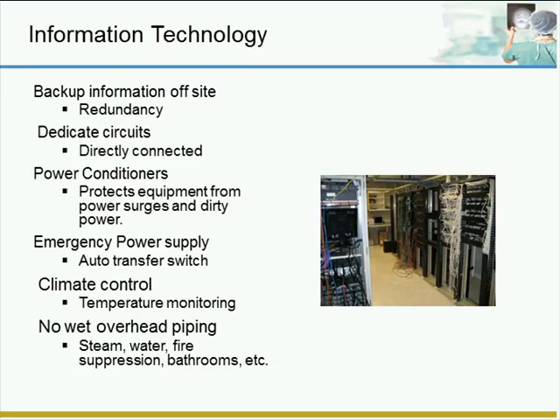Information technology, IT rooms. Critical and confidential information should be protected from being lost. You should be backing up information off-site daily or weekly. If possible, use dedicated circuits. By using dedicated circuits, there's less chance of electrical failure. Power conditioners: you should have a power conditioner at the incoming feed to the IT room. And again, emergency power supply or battery backup for proper shutdown of the equipment.